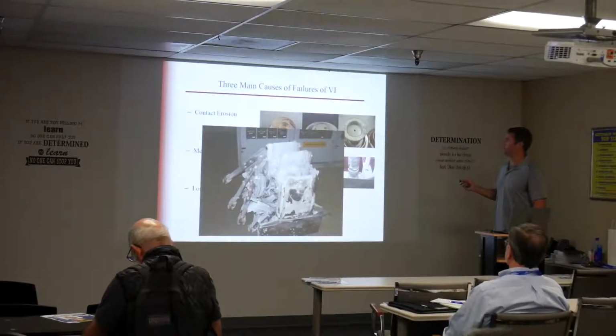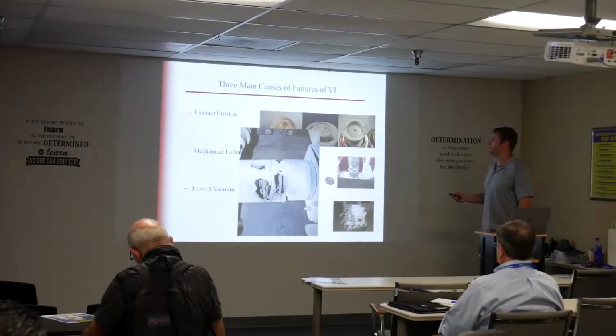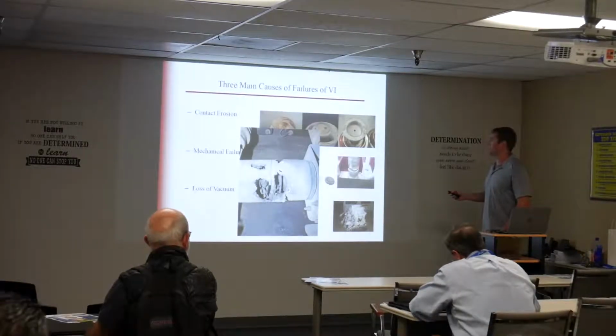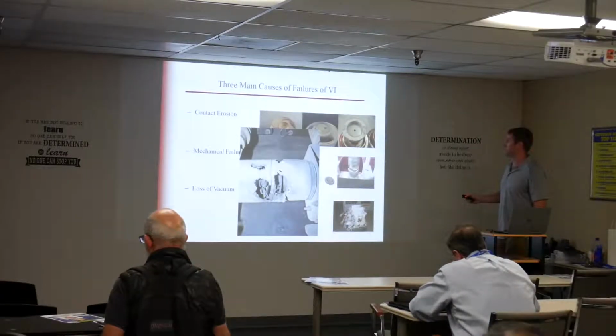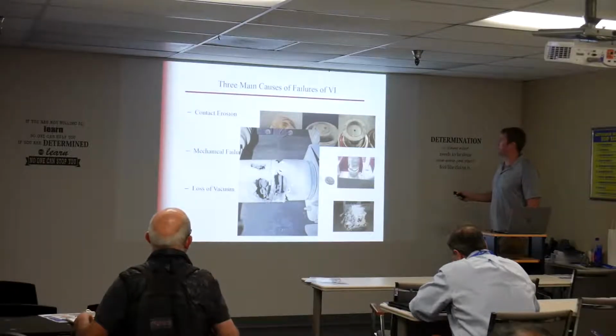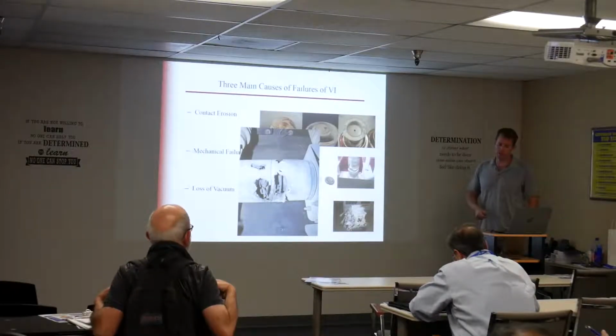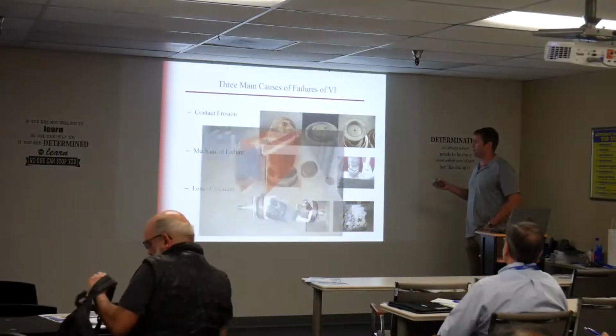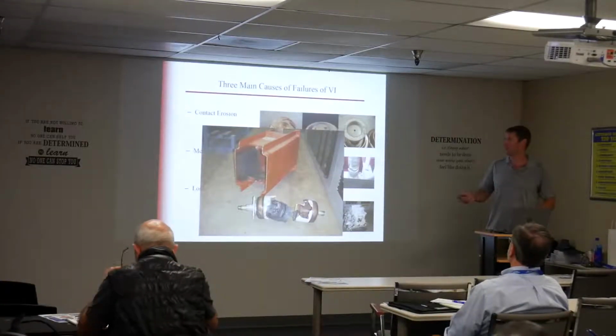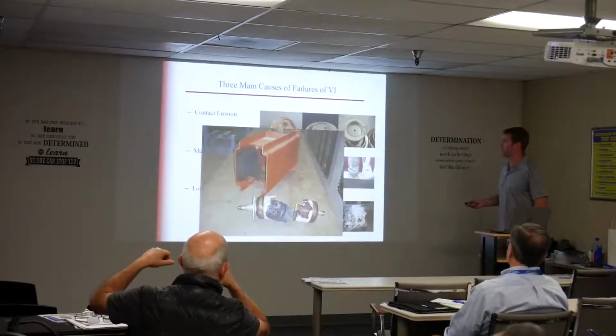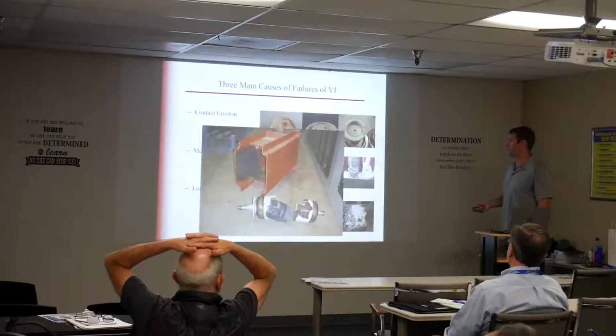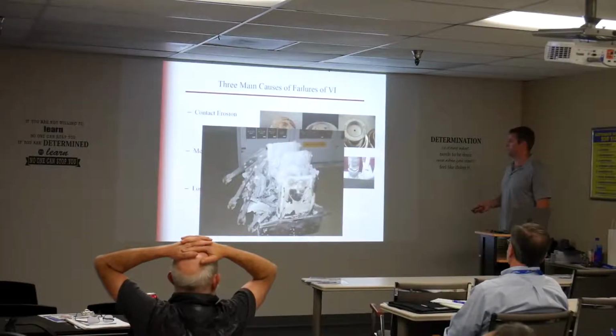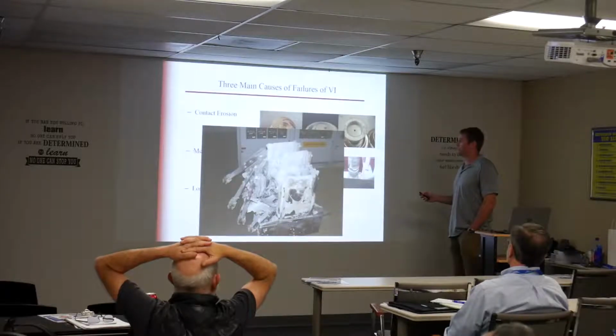Then the 3rd main cause of failure is loss of vacuum. As you know, most breakers are closed the majority of their life, so they really aren't called upon to interrupt any faults or interrupt much load. So most of them are closed. Most operations are done during maintenance. So like I said, if this breaker is just closed for 20 to 30 years, eventually enough gas is going to leak into it. When it's called upon to interrupt a fault or open under load, it doesn't have the insulating capability to do that.